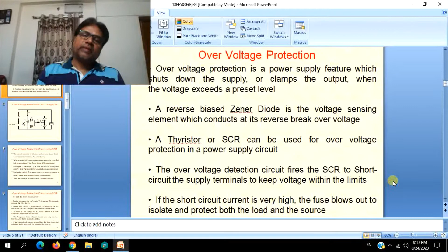In this slide is shown a typical overvoltage protection circuit using SCR, which is used for AC mains. Just consider it is a single phase AC supply. The load gets its current and voltage in the normal path. The source impedance ZS is shown in series, and obviously a fuse is connected in series. So this is the actual circuit where the load gets its voltage, via the source impedance. The source impedance will obviously be as small as possible.